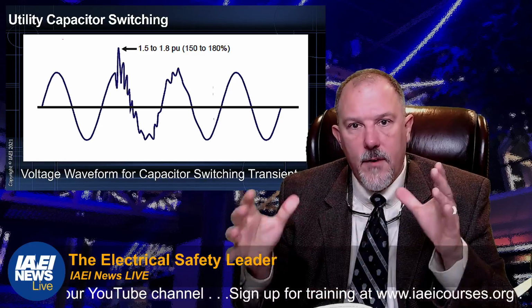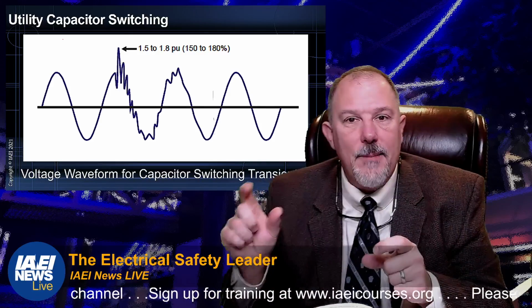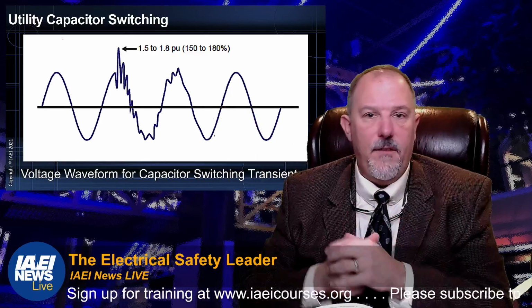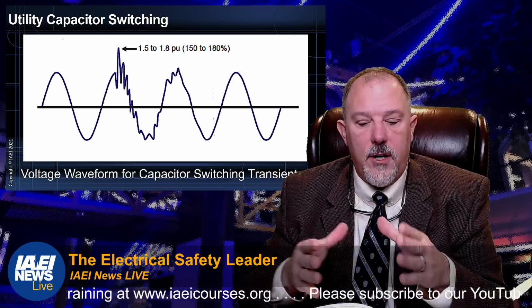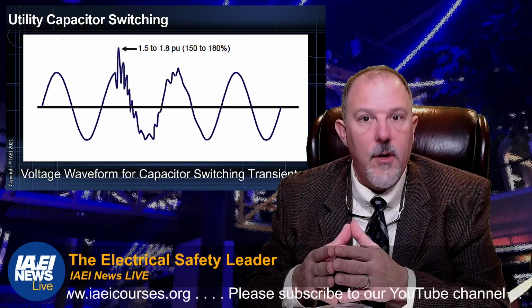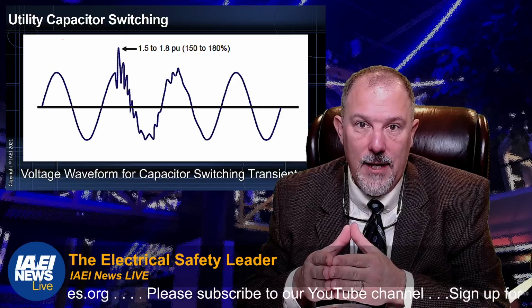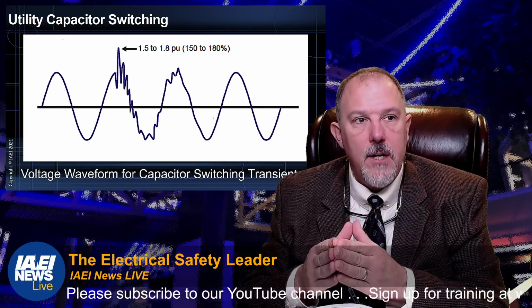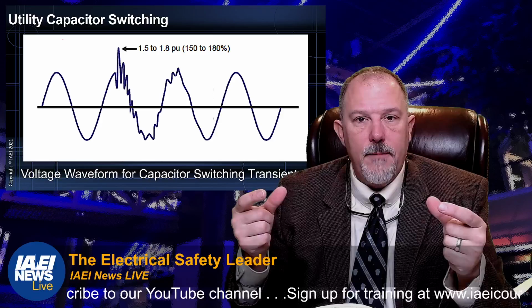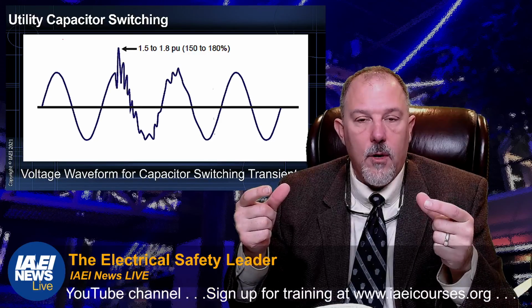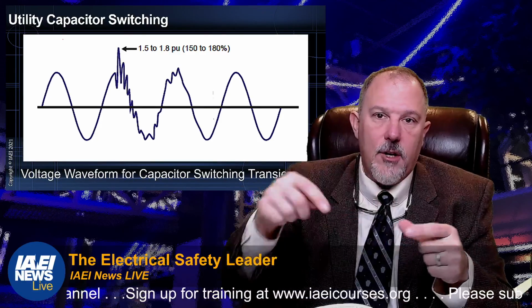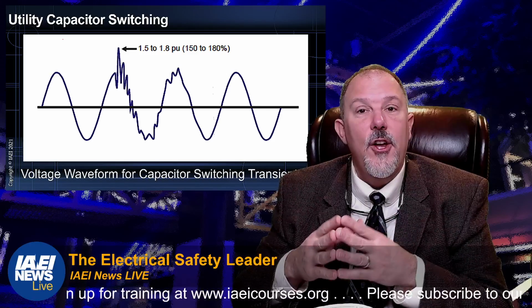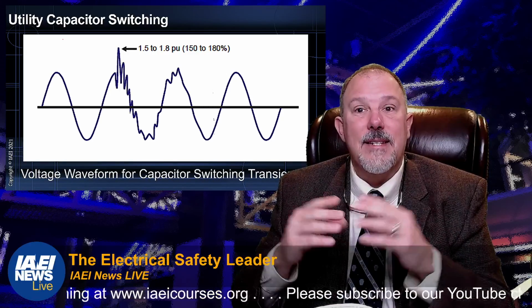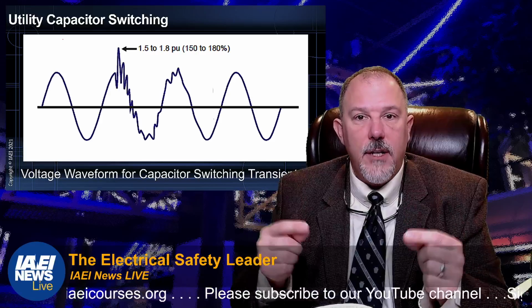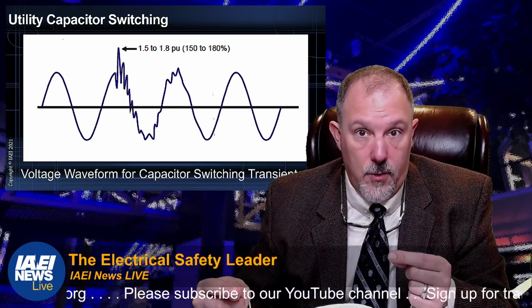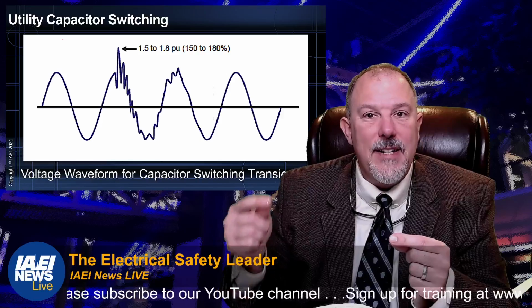So we put all of our equipment up, and we captured the event in the morning, and we captured the event in the evening, and it was a ring wave. And the issue was, because it was such a new development, the ring wave was very pronounced. And what was occurring were power strips, those multi-tap units that you put on your TV and whatnot, that have voltage protection in them. Those units were designed in a way that they shunted current not to a neutral, but to the equipment grounding conductor.